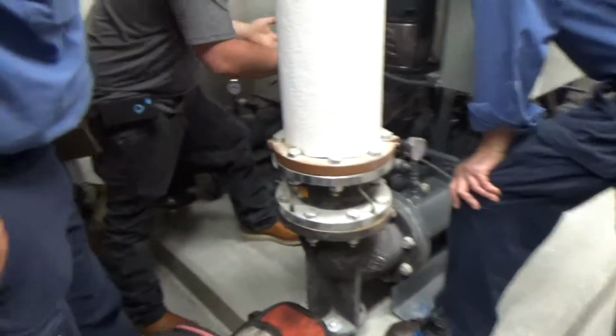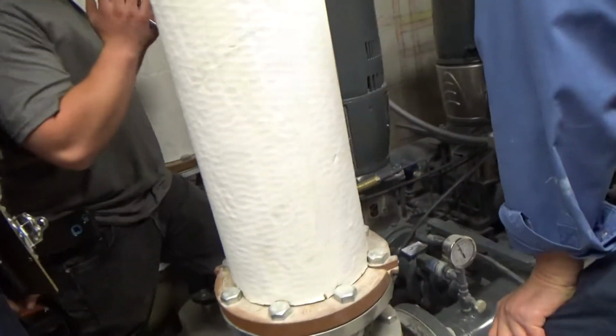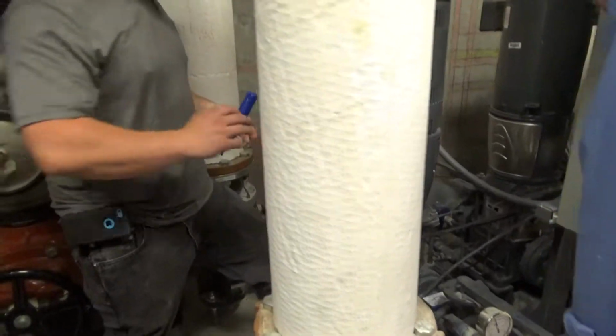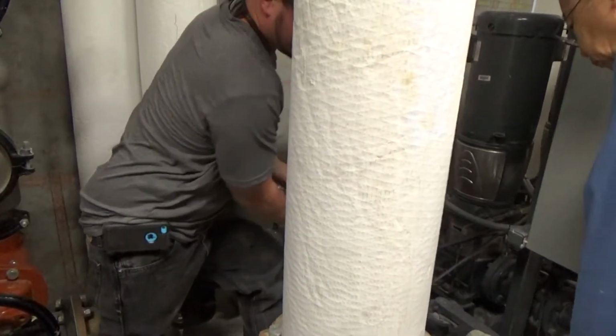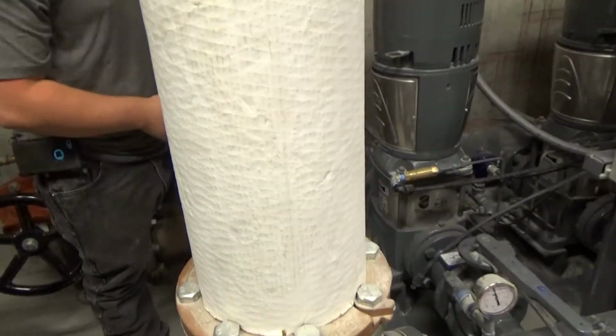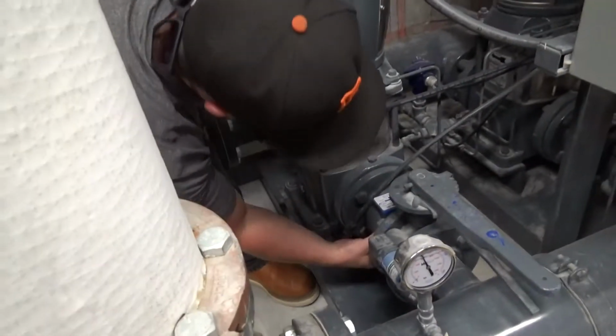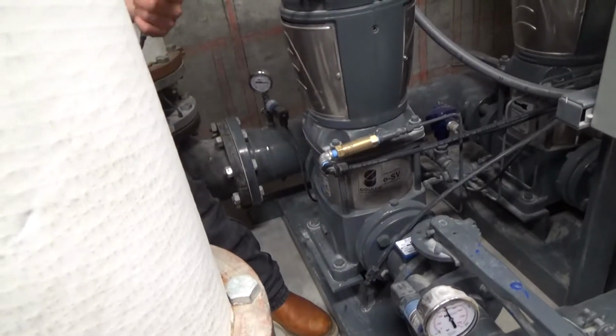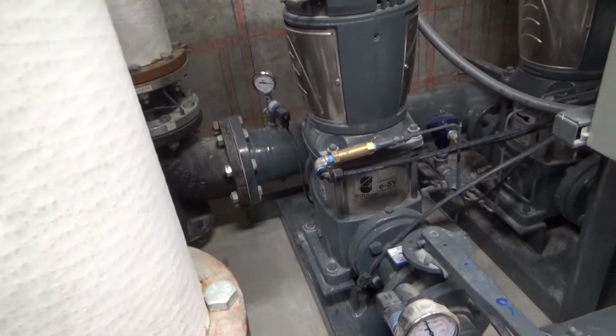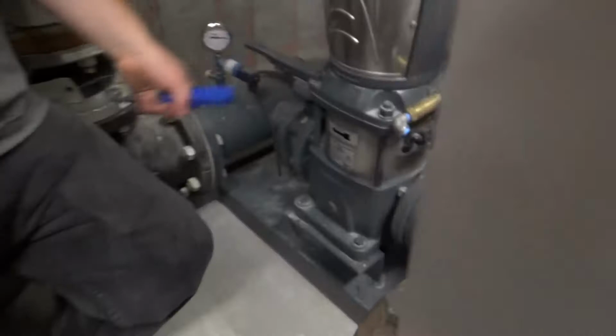And what's funny is they put the nameplate on there, but it's kind of deceiving because it's facing that way, so everybody thinks, is it backwards? And it's like, no, because you would think the nameplate would be facing the direction of flow, but it's correct. They also have an arrow on the bottom that shows the direction of flow. So if you guys ever have to take that out, just make sure the direction of flow is correct.